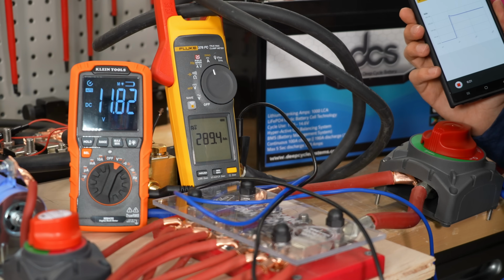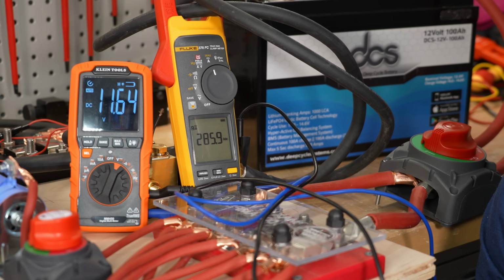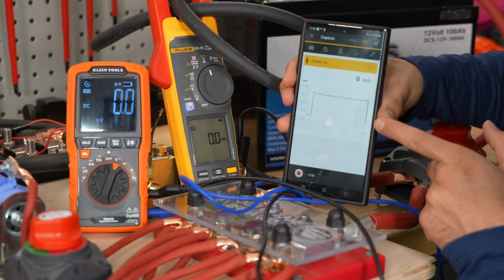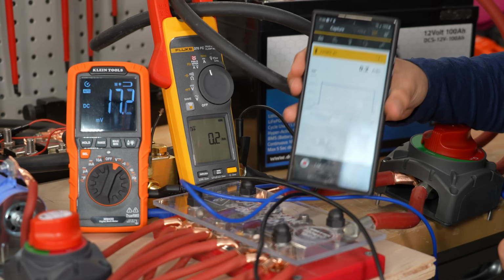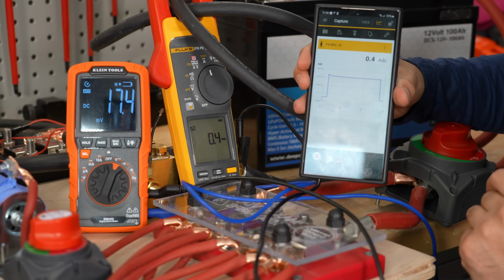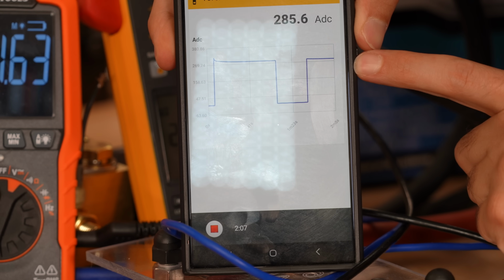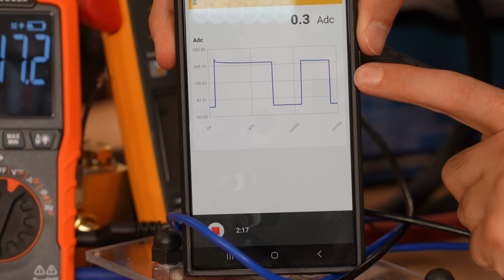300 amps... 14, 15, 16... 54, 55, all right it's been over a minute. Oh, there we go, we got a disconnect. It actually works, fantastic. Then it reset itself and it's drawing 285 amps again. And look at that, it disconnected again. This is what you want it to do if you're trying to start an internal combustion engine.